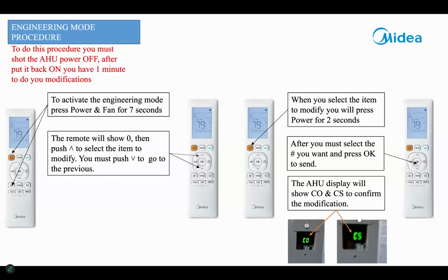Once you see COCS, back out of engineering mode: press and hold the fan and the power button for 2 seconds, which will back you out of engineering mode. Turn the power off to the air handler, turn it back on, and the parameter has been changed.